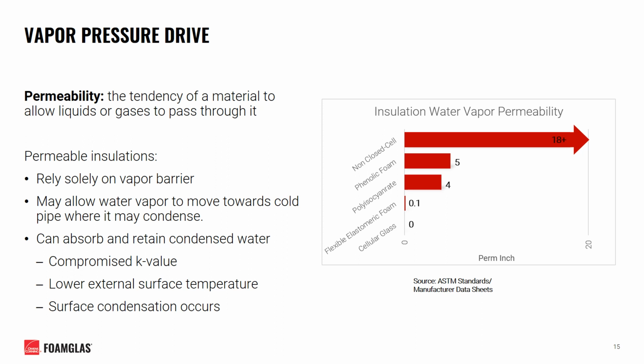This condensed water can then be absorbed and retained into the insulation, which can compromise the K value, leading to lower external surface temperatures of the insulation. And you end up with a situation where you not only have condensation taking place on the chilled water pipe, but potentially on the external facing of the insulation itself. As you can see on the right, closed cell insulations typically tend to have much lower water vapor permeability values than open cell and granular type insulations.